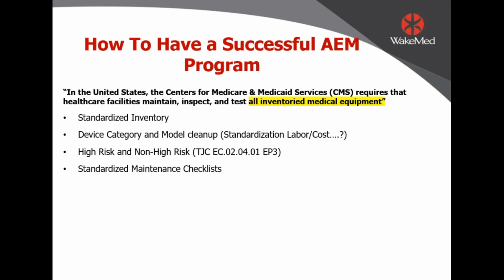Standardized maintenance checklists. If you are going to put a device on AEM, your technicians need to know what steps you're taking. What are you doing differently? If you're adding steps, you have to make sure that technician A and technician B are doing the same thing. In our CMMS, we created a rule that for all our PMs, we could put in our checklist. So whatever we decided was the PM, it was a checklist, and you can't close out that work order. You can't hit close unless everything's checked off. The PM has to be completed.